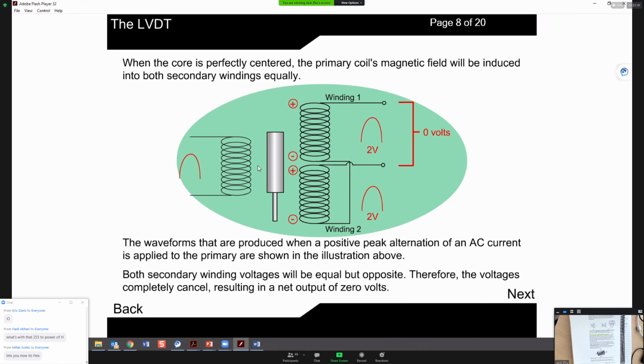Here you can see they induce a voltage, and both secondary coils, when the core is right in the center, both induce 2 volts on the secondary coil. But because the secondary coils are wired together backwards, the output from this terminal will be 0 volts.